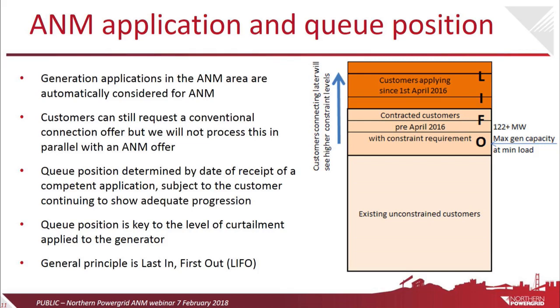So moving on to ANM applications and the queue position. If you do apply to get connected to the Driffield network, we'll basically automatically consider you for an ANM connection, but we would discuss this with you first. So we have some commercial engineers that know this network quite well, and when they see that they're getting a request for a connection of generation, particularly to this bit of the network, they'll automatically look into an ANM solution and an offer. We will provide you with either a conventional offer or an ANM offer, but we won't provide both at the same time. However, what we can do is give you an indication of the likely costs of a conventional connection, i.e. the one with reinforcement and outside the ANM scheme, and an indication of an ANM connection, how much that will cost, to help you decide which type of offer you'd like.